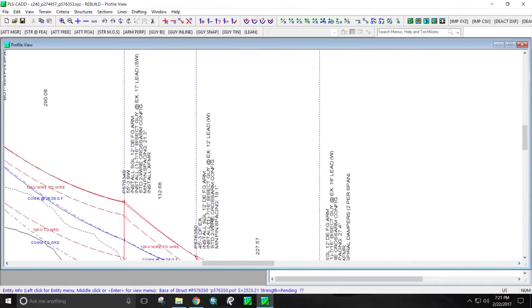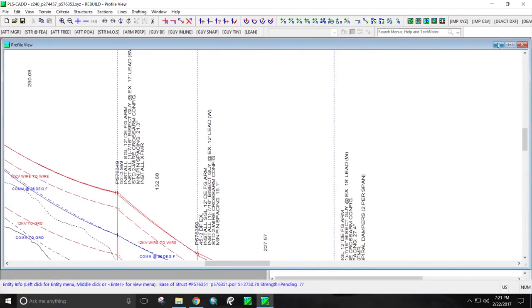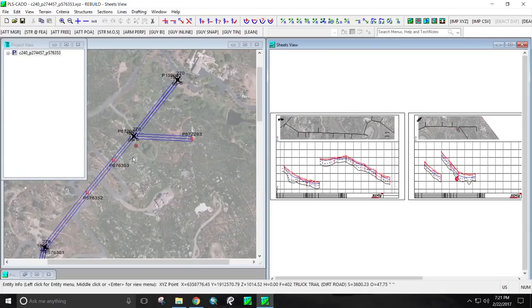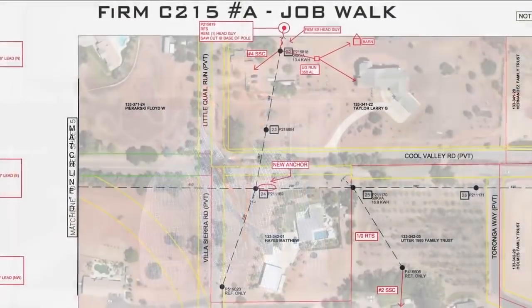One of my responsibilities on FiRM is to oversee the design, the structural capacity utilization, the PLS-CADD. So one of the strengths associated with PLS-CADD is due to this more accuracy doing this nonlinear analysis, it allows us to perhaps elongate and optimize the life of these assets that we're installing. So we're not shooting for just a 20 or 40 year life, we're really trying to optimize to the 80, 100 year perspective.